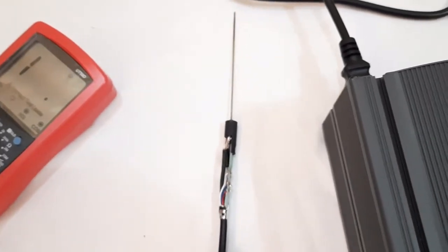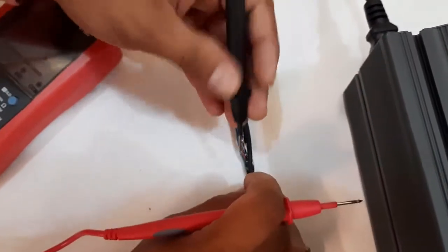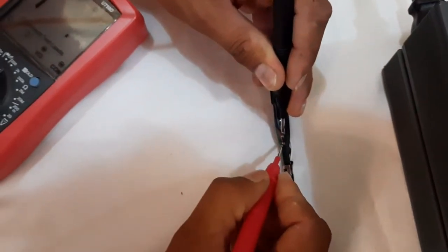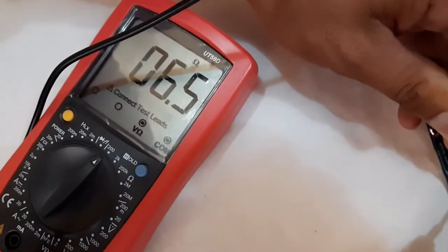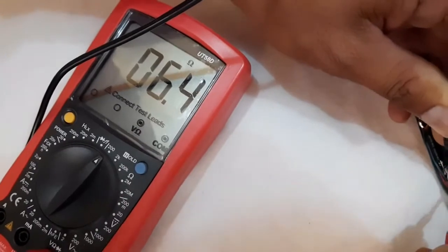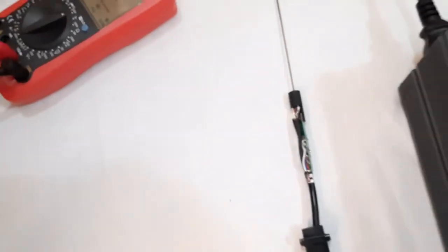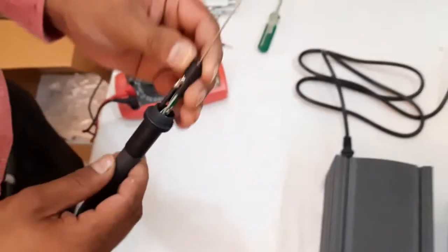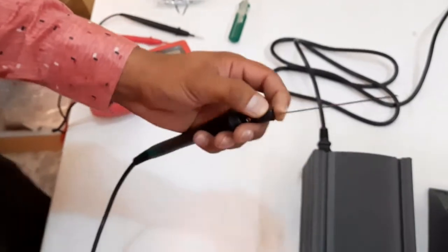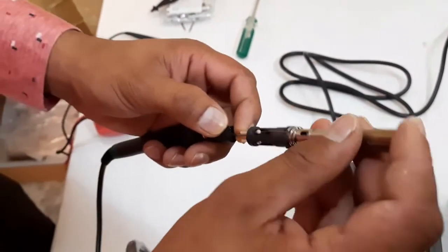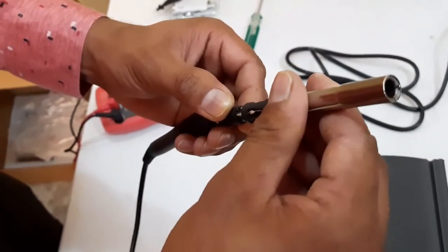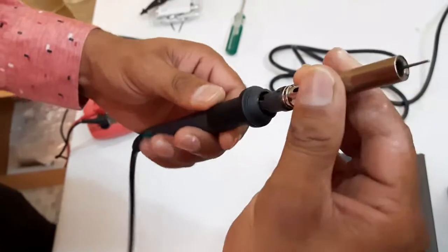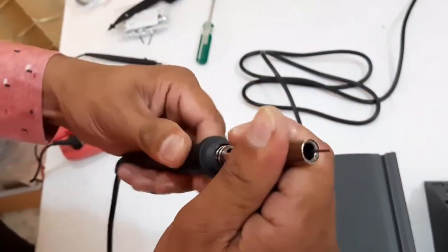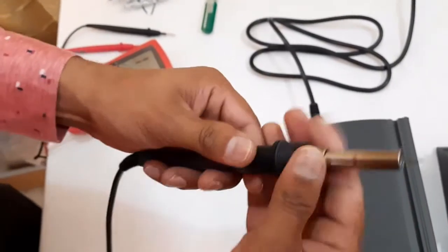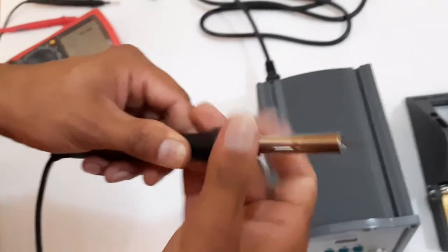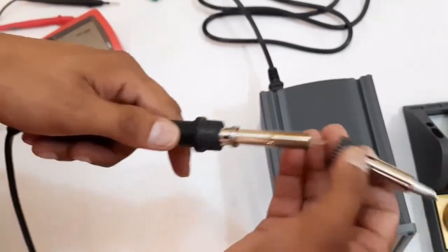Now we will again check the resistance between these two wires, and it should be less than 10 ohm. Yeah, we can see the resistance between these two wires is less than 10 ohm. It means now this sensor is all right, and now we will just fix it. We need to just insert this heating element again. And reverse the process. We will first now fix this nipple, then this nut and barrel assembly along with the soldering bit.